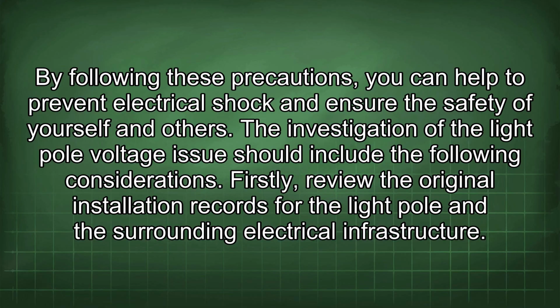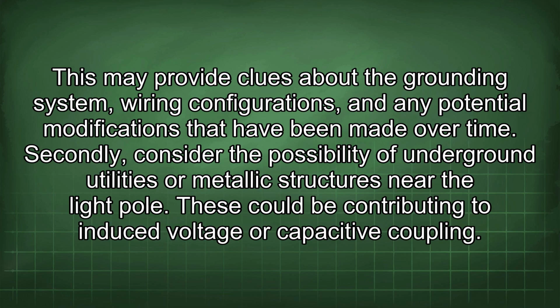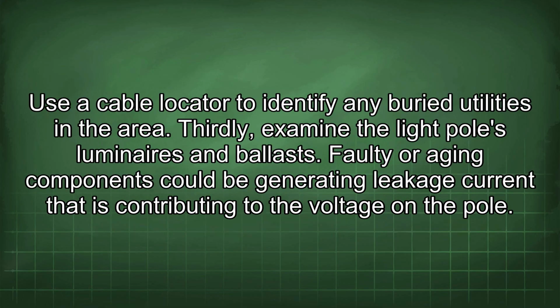The investigation of the light pole voltage issue should include the following considerations. Firstly, review the original installation records for the light pole and the surrounding electrical infrastructure. This may provide clues about the grounding system, wiring configurations, and any potential modifications that have been made over time. Secondly, consider the possibility of underground utilities or metallic structures near the light pole. These could be contributing to induced voltage or capacitive coupling. Use a cable locator to identify any buried utilities in the area.